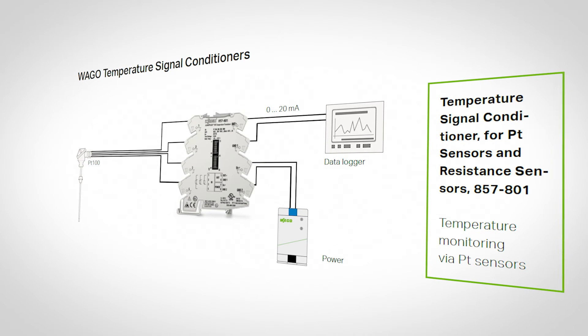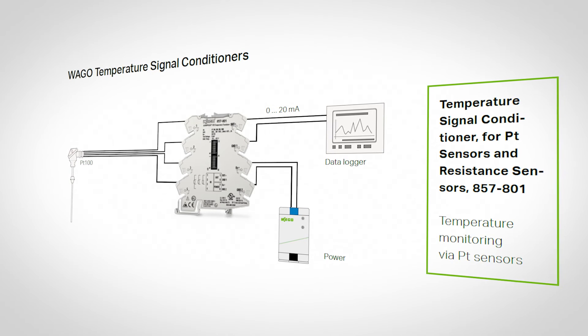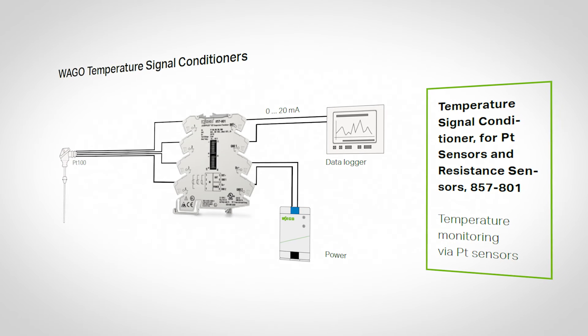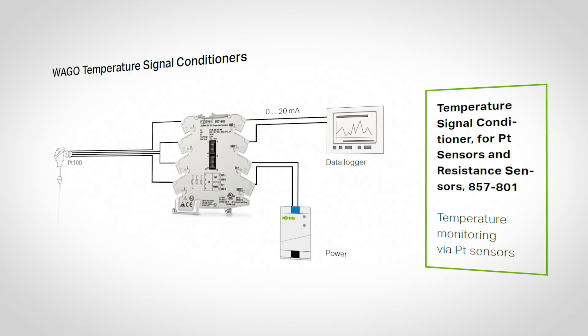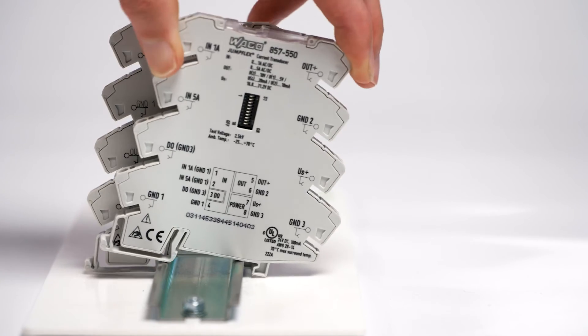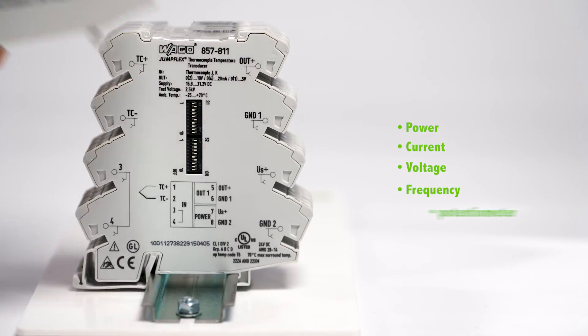Temperature signal conditioners: quite simply, these devices take inputs from RTDs — resistive temperature devices — such as PT100 probes or thermistors, and convert this into a 0 to 10 volt or 4 to 20 milliamp analog signal.